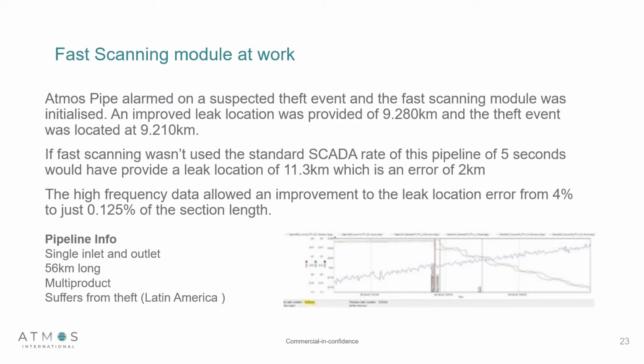If fast scanning wasn't being used and we were using the standard SCADA rate of this pipeline of 5 seconds, we would have provided a leak location of 11.3 kilometers, which is an error of 2 kilometers. By utilizing this new module with hardware that allows us to sample at higher acquisition rate, we were able to improve the leak location error from 4% to just 0.125% of the section length. And to give you an idea of what this pipeline was, this section of pipeline was a single inlet and outlet. It was 56 kilometers long, multi-product, and as I stated before, it suffers from theft events. So this just shows you that a historical disadvantage of flow balance has been dramatically improved to almost the level of a negative pressure wave system.